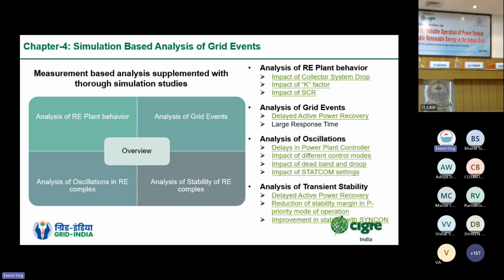The first one is the analysis of the RE plant behavior: how RE plants used to behave and why there was a difference between the simulated RE plant model and the actual plant performance. We came to know that the impact of collector system drop was one of the possible gaps where RE plant behavior and the actual plant behavior differed. Then there was an impact of K factor. K factor is a parameter in the voltage controller. What K factor has been given and what K factor was implemented at the site were different, and that caused a difference in the RE plant performance.